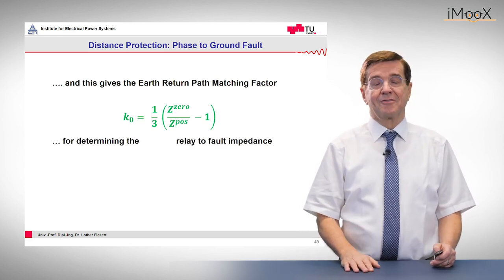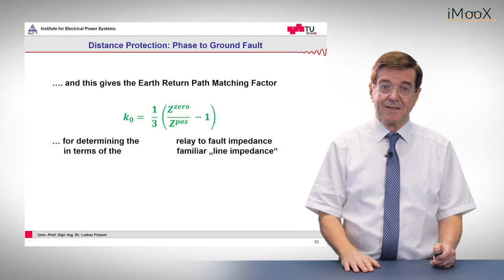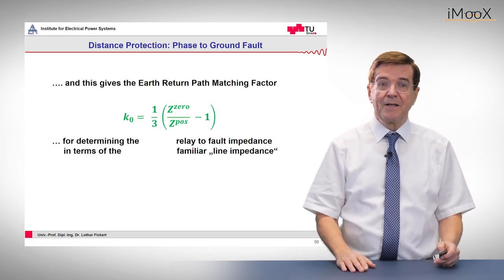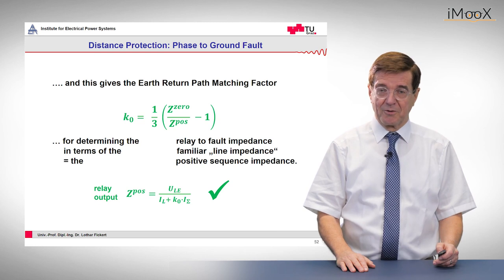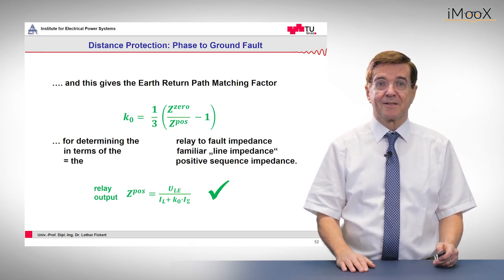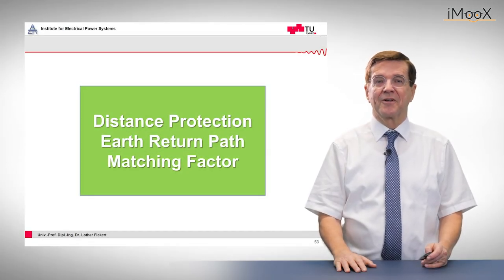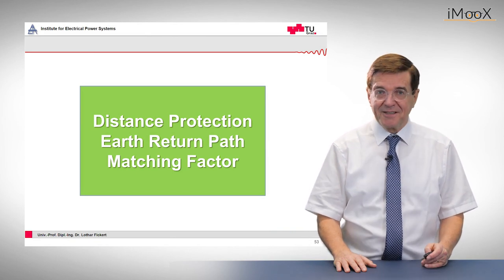Then we can determine from this the relay-to-fault impedance, which is the familiar line impedance. This is used for the relay output, which triggers the relay and determines the protection behavior. So this was today's lecture about distance protection with the focus on the earth return path matching factor. Thank you very much.